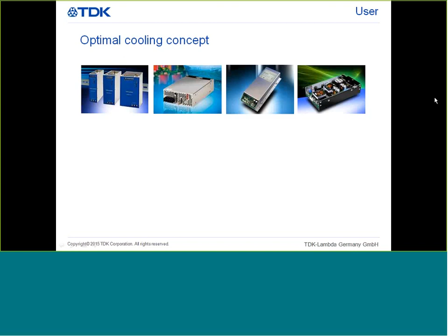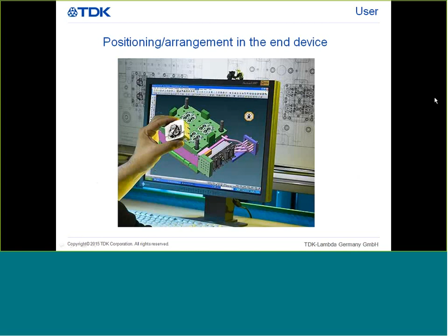So what is the really effective way of cooling of a power supply in terms of the specified requirements? To find the best place for the power supply in the end device, the most suitable place would be an area with the best heat dissipation and air circulation. What is the temperature difference between ambient and inside? The more tight the housing, the more important the cooling concept. Here an example with housing completely closed and with sufficient cooling slots.